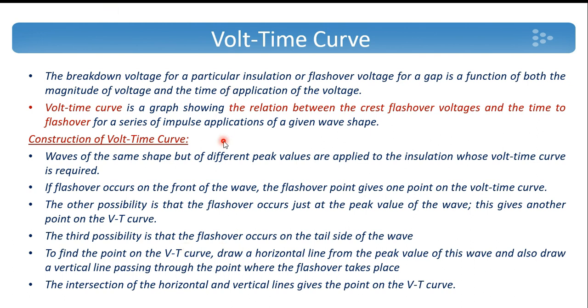In order to get the insulation coordination level, the volt-time characteristics of different insulation levels of different equipments are studied. The breakdown voltage of a particular insulation or flashover voltage between a gap is a function of both magnitude and time of application. Even if the voltage is higher, if it is for a very short duration it may not cause flashover in the system. Since it depends on both voltage and time, the volt-time curve is drawn.